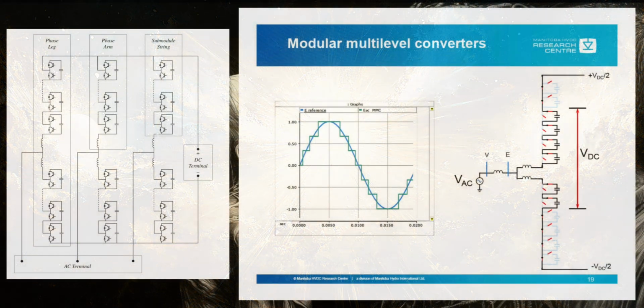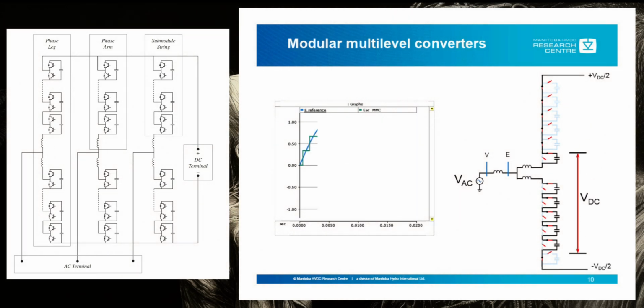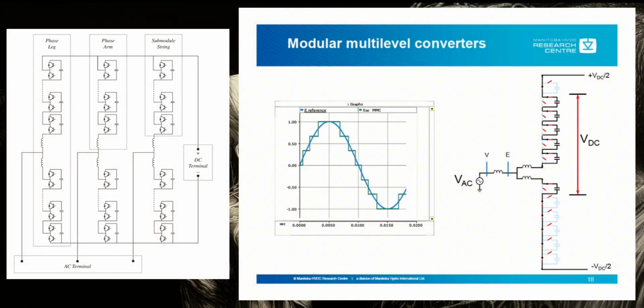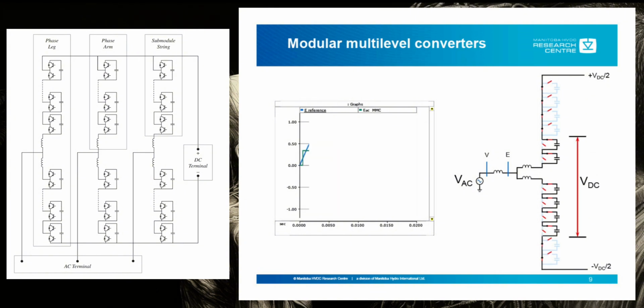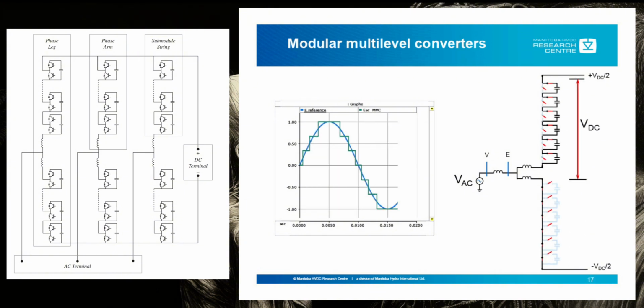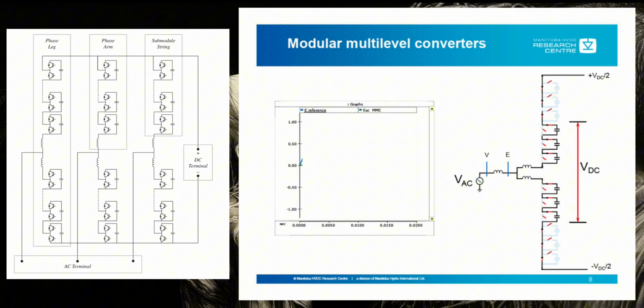Most users of VSC HVDC converters will use half-bridge MMCs. Now, the advantage to MMCs in general is their high efficiency, modular scalability, and superior harmonic performance without the need for bulky filters. Their ability to generate a near sinusoidal waveform reduces switching losses and improves grid integration.